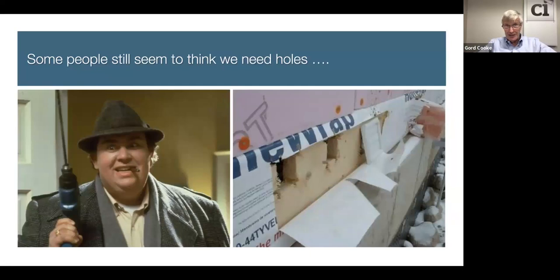And if it's an air quality concern, think about that wildfire smoke situation. The best possible scenario is you live in an incredibly tight house with a mechanical ventilation system that has a HEPA filter or a MERV 13 filter, which most ERVs now do. If it gets really bad for short periods, you can turn off the ventilation system and you're not impacted by the outside air. So be really clear: the tighter the house, the better air quality control you can have, because you can control the amount of air moving into the house and filter pollutants that might be coming in.